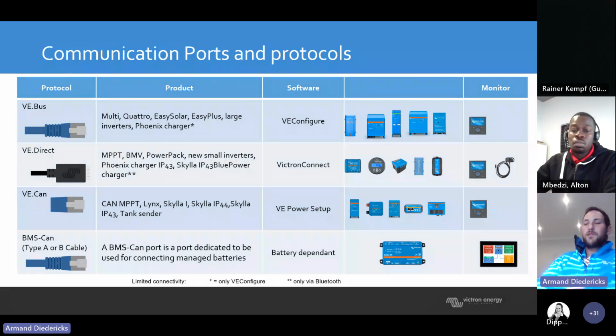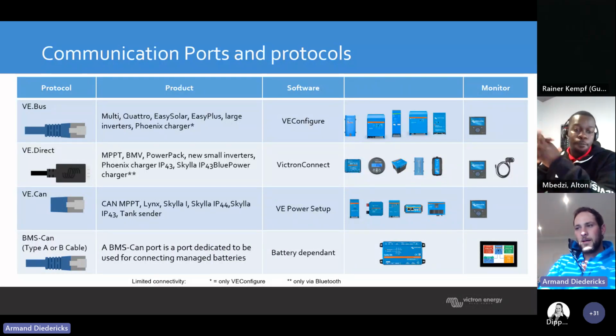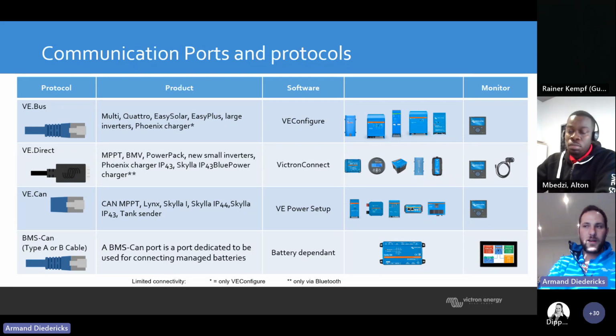Then you've got your BMS CAN type A or B cable, depends on what battery you have installed. If you've got a Freedom Won, a Solar MD, BSL, whatever the case may be, Hubble, Pylontech, there are multiple batteries, so it all depends on what protocol your battery talks to, while the software stays the same. If it's a type A cable, you plug in a type A. Normally the cables come with the batteries, so you just plug it into the BMS and go program the GX device on whatever protocol it is.